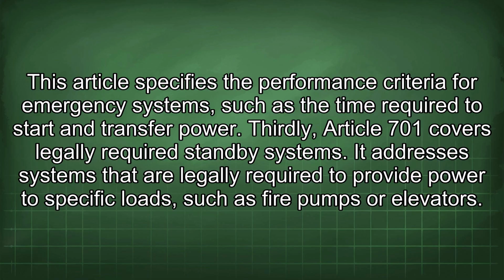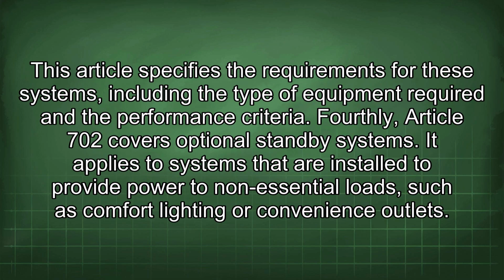Thirdly, Article 701 covers legally required standby systems. It addresses systems that are legally required to provide power to specific loads, such as fire pumps or elevators. This article specifies the requirements for these systems, including the type of equipment required and the performance criteria.